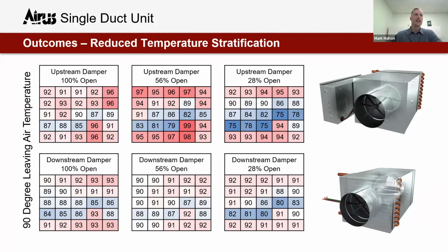Another great byproduct here, the reduction of temperature stratification. So we can see with a traditional single duct box, this kind of blue band that carves through the middle when we look at temperature stratification and kind of lack of mixing. The more closed the damper is, the harder it is for that hot air to have immediate access back into the center of the ductwork. All of this is measured at 2 feet downstream of the discharge of the terminal.